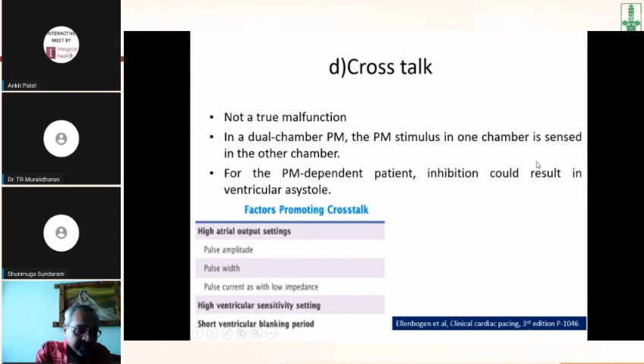So this occurs classically with high atrial output settings, when we have an amplitude something like 5 or 6 or a pulse width greater than 0.7, and a very high ventricular sensitivity setting. Then the crosstalk can occur. So meaning when you pace the atrium, it can be sensed by the ventricle and that can get inhibited.